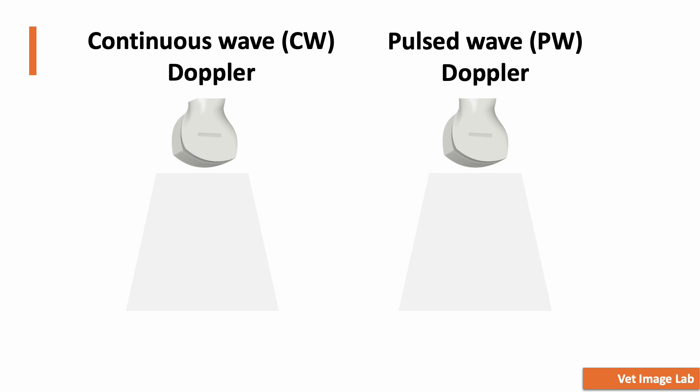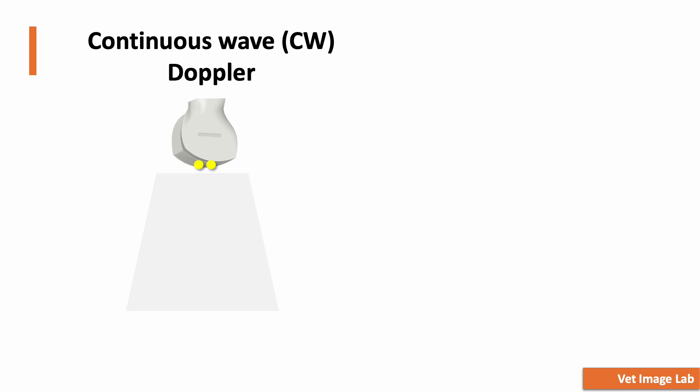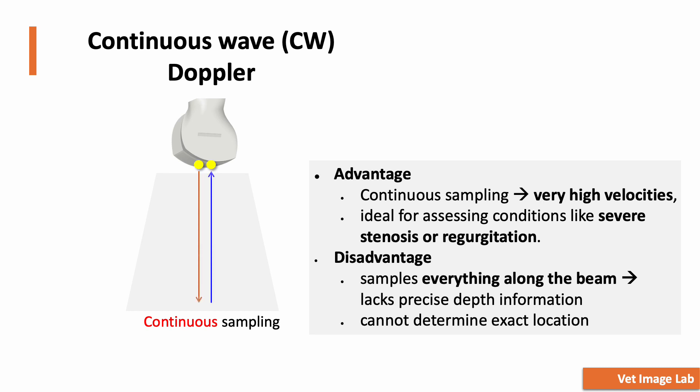Let's talk about continuous wave, or CW, Doppler first. CW Doppler uses two crystals — one continuously sending ultrasound waves and the other continuously receiving them. Because it continuously measures all blood flow along the beam, it can detect very high velocities, making it ideal for assessing conditions like severe stenosis or regurgitation. However, since it samples everything along the beam, it lacks precise depth information, meaning we cannot pinpoint exactly where the velocity is coming from.